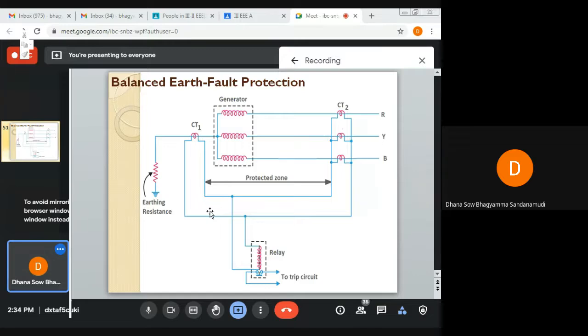Whenever we want to protect a small size alternator or generator, the engineers have seen that the neutral point, this is the neutral point, and this is the generator three-phase winding. The neutral point of the three-phase winding is often connected internal to a single terminal. So it becomes difficult to use Merz-Price circulating current protection for small size generators.